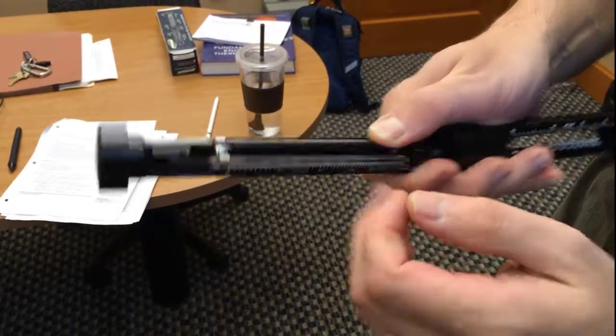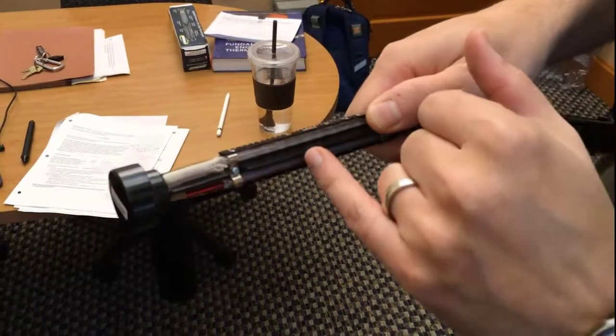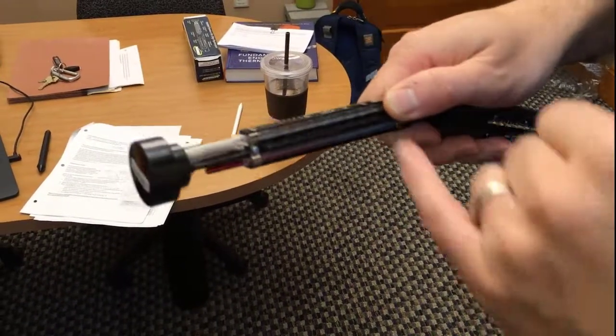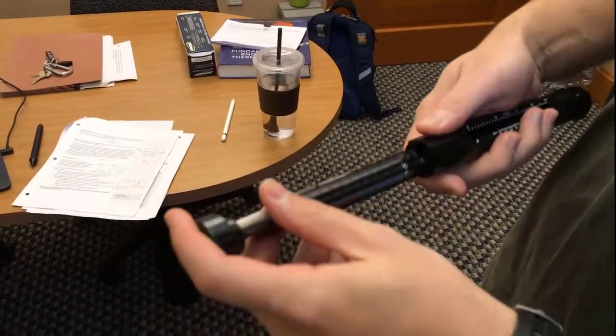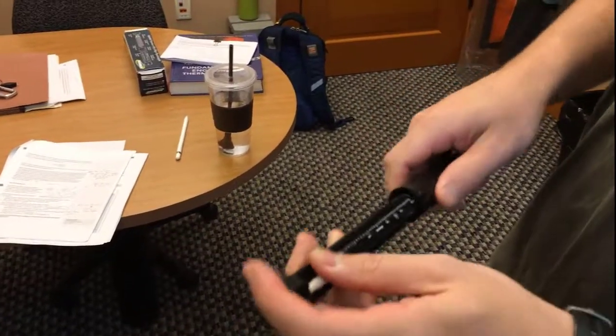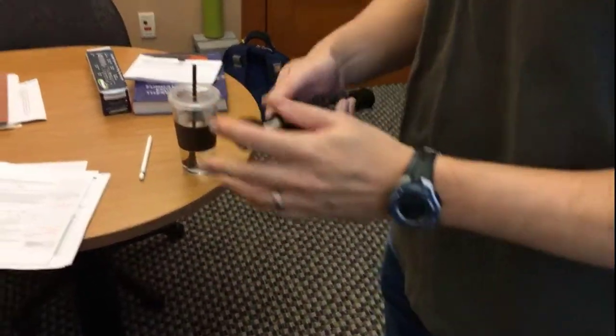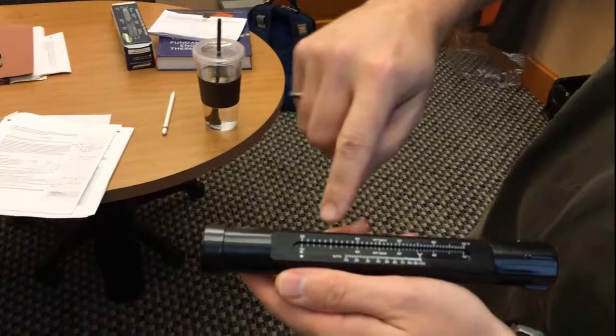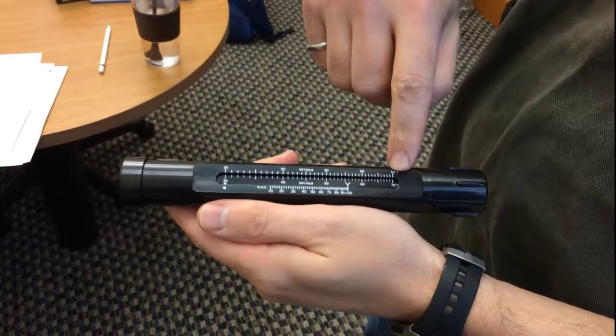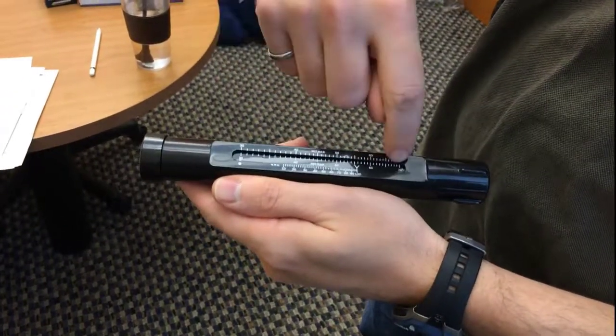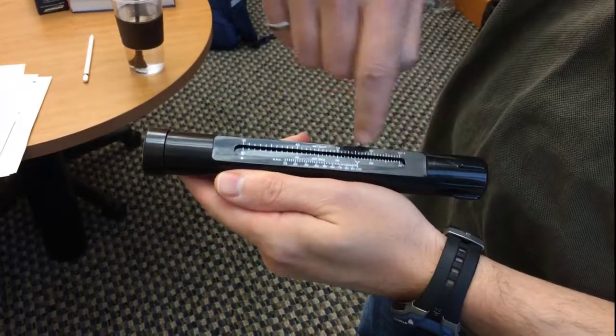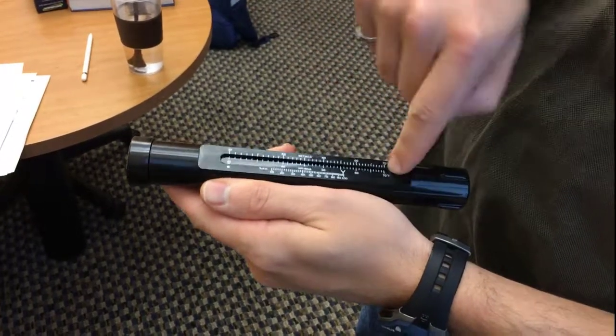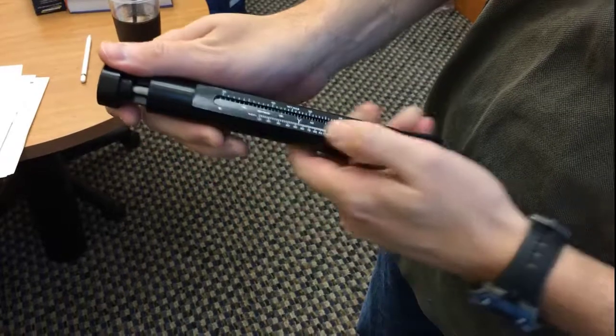We got 70 on the dry bulb and 58 on the wet bulb. So what we do now is close it and look at these scales. The dry bulb was 70 and the wet bulb was 58. We're going to line up the 70 with the 58. We get the 70 on the dry bulb.